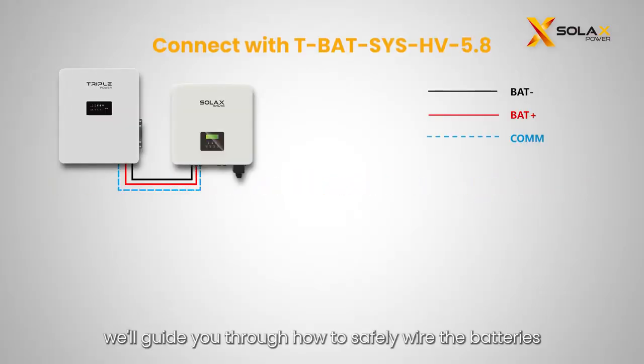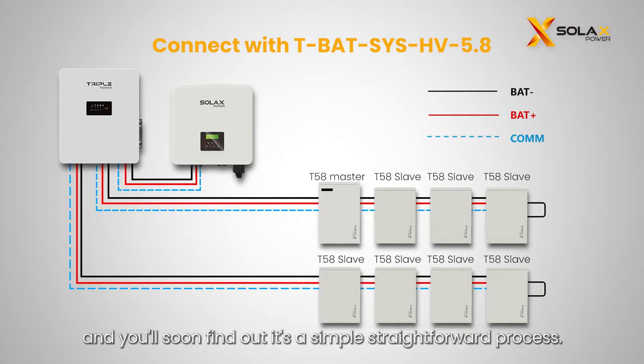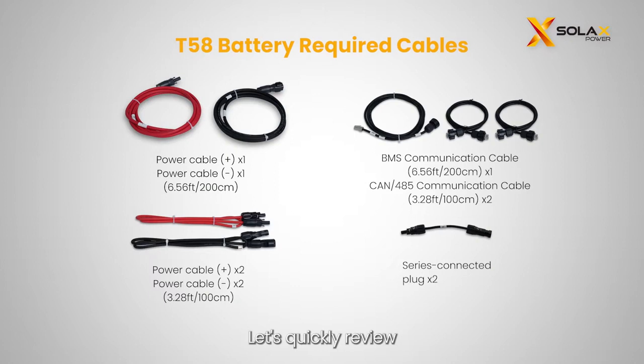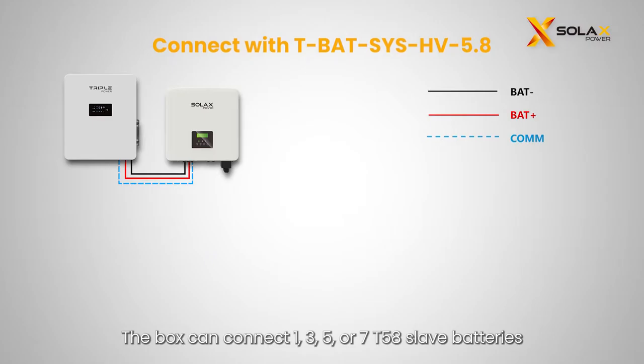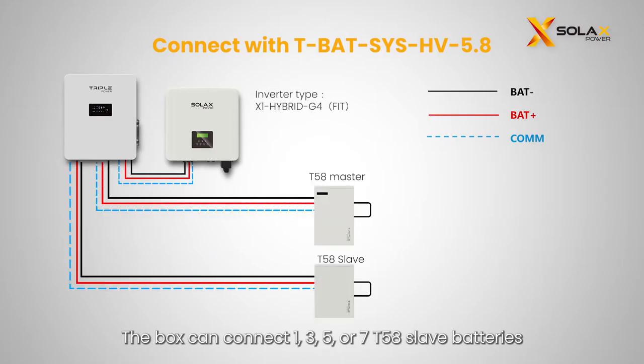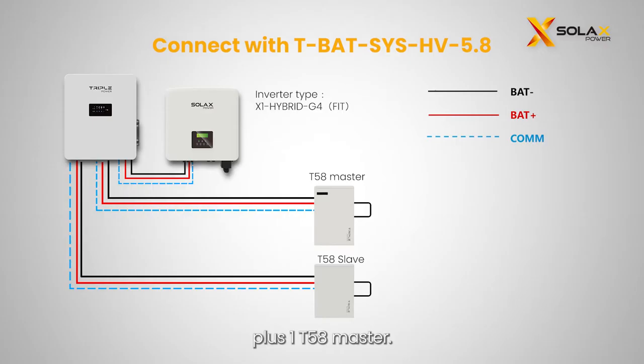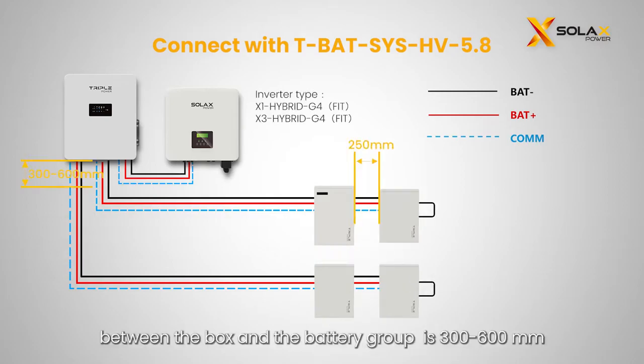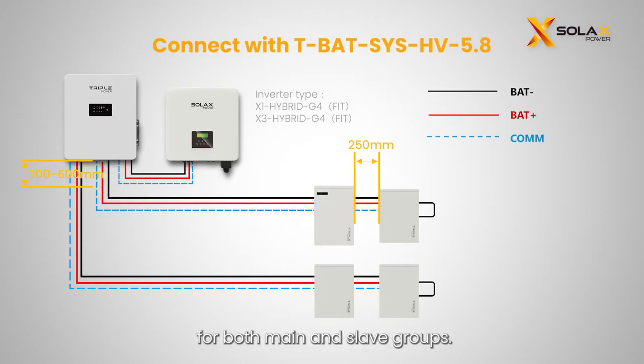In this part, we'll guide you through how to safely wire the batteries, and you'll soon find out it's a simple, straightforward process. Let's quickly review which cables are needed to complete the T58 battery wiring. The box can connect 1, 3, 5, or 7 T58 slave batteries plus one T58 master. It is suggested that the battery be connected from left to right. The recommended installation distance between the box and the battery group is 300 to 600 millimeters for both main and slave groups. The recommended installation distance between battery modules is 250 millimeters.